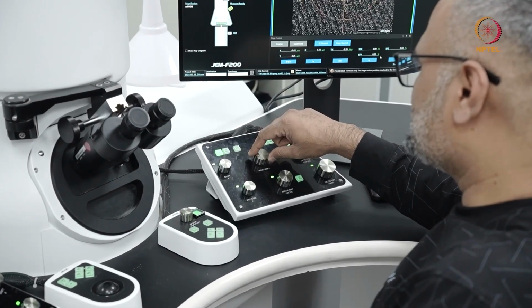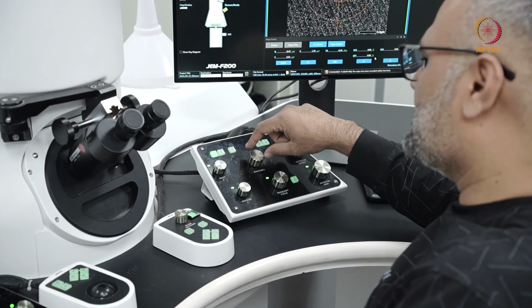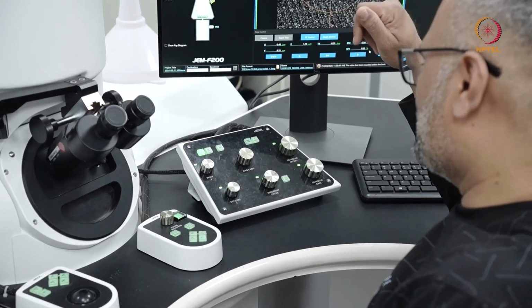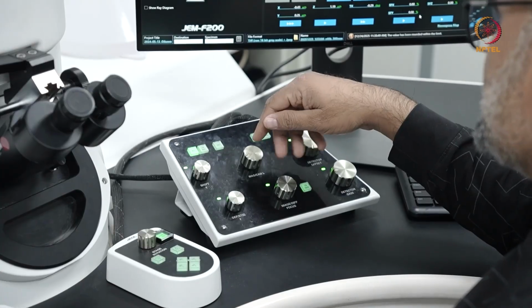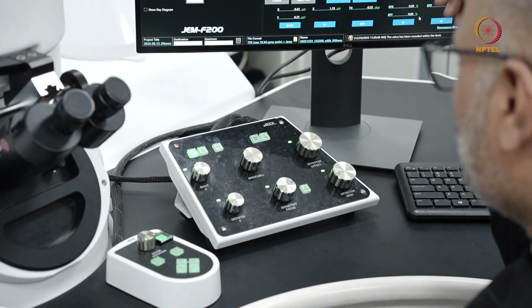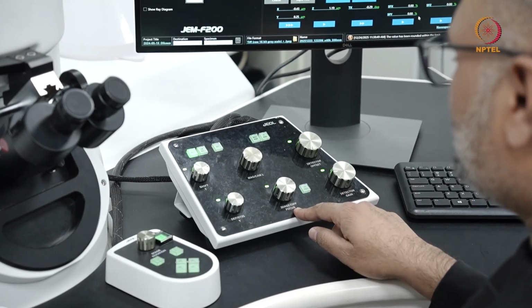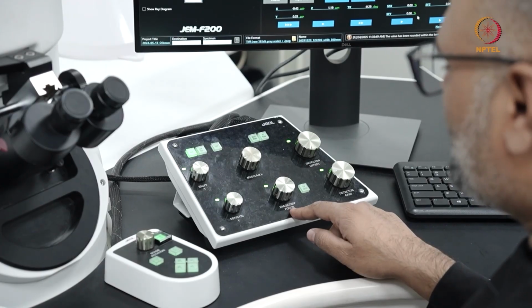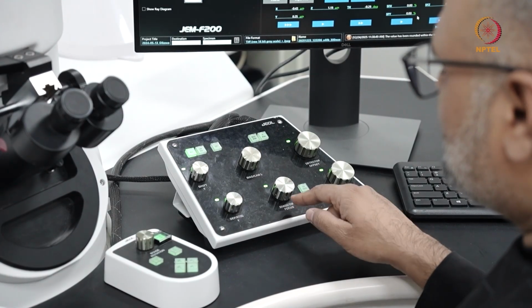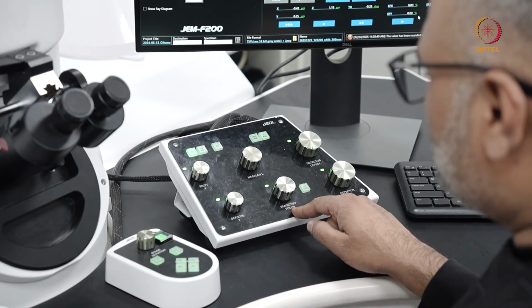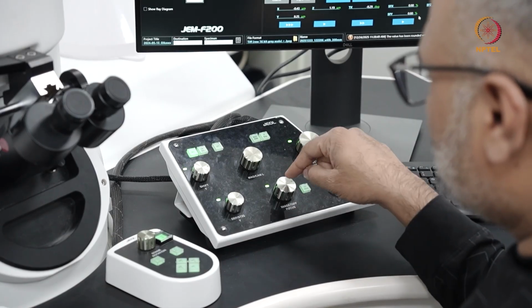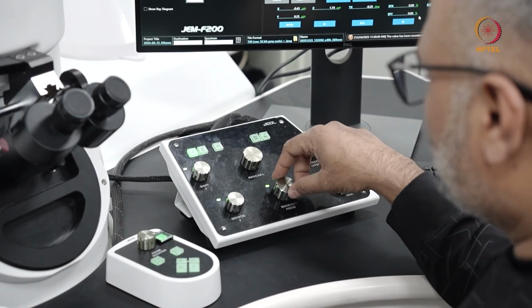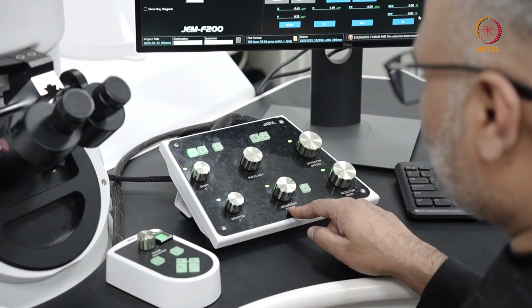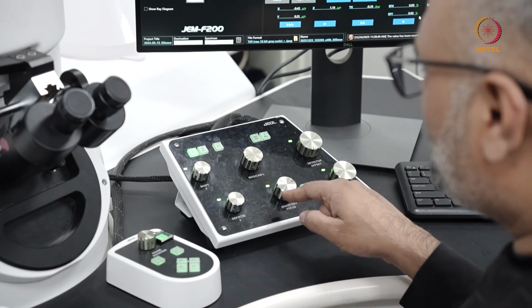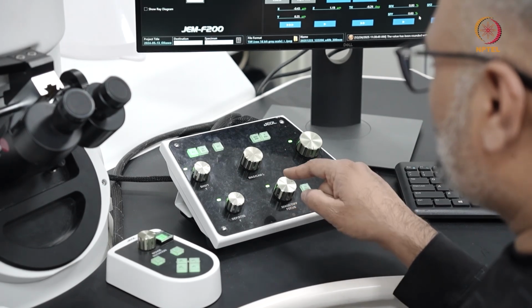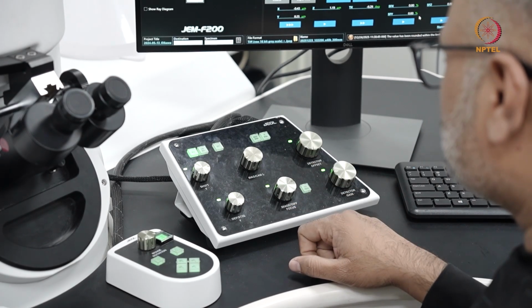So when I turn this, I can go anywhere from 2000 all the way to 1.2 or 1.5 million X magnification using this. Now here you have the image or diffraction focus knob. The key difference here from the other console which you saw on the 2100 is, it is the same knob to tune the focus for the objective lens, whether it is in imaging mode or in diffraction mode, to adjust the focus of the illumination lenses.